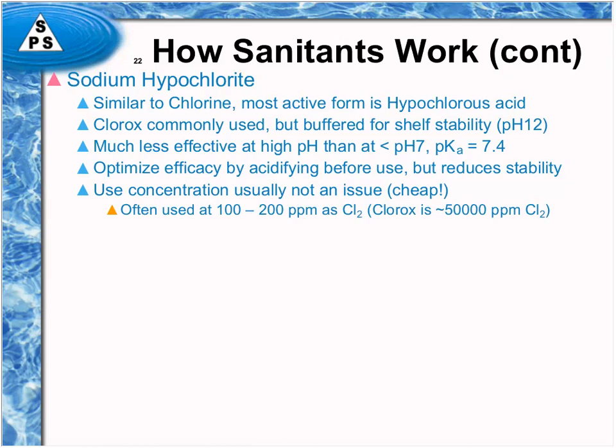And as a periodic sanitant, I've seen it diluted only about tenfold or so. So you have sometimes as much as 5,000 ppm chlorine. And that's usually not a problem unless the materials aren't compatible with it, because the hypochlorite is a very cheap compound, and so you can really nuke it with the hypochlorite treatments.